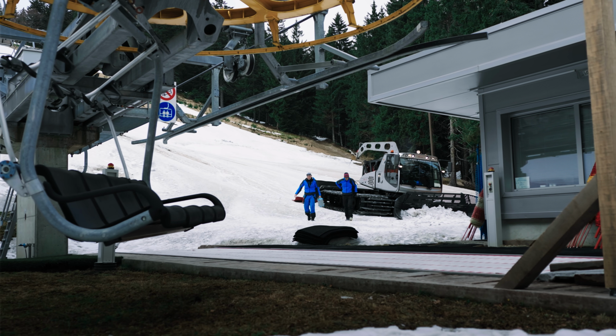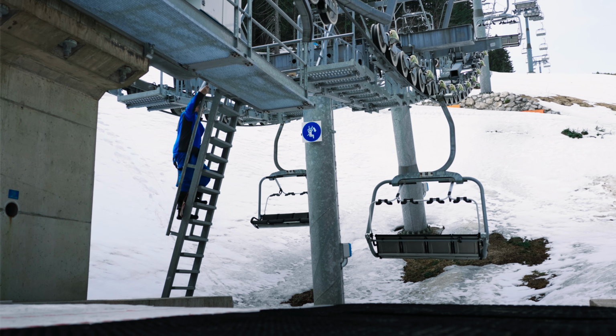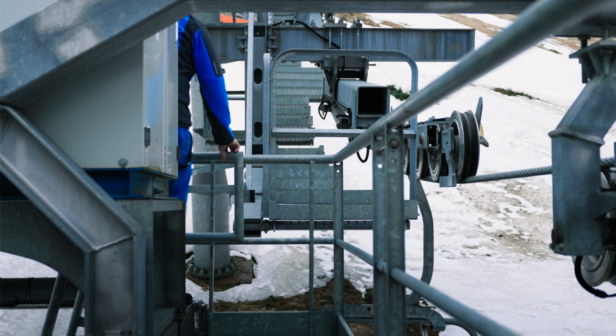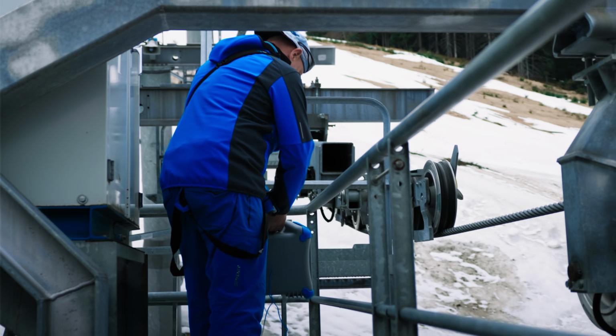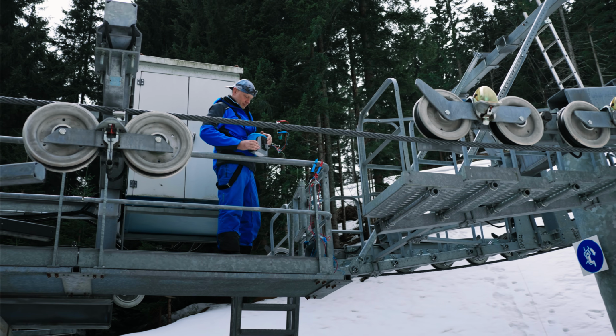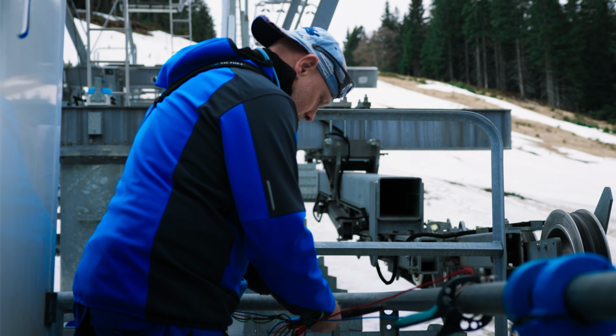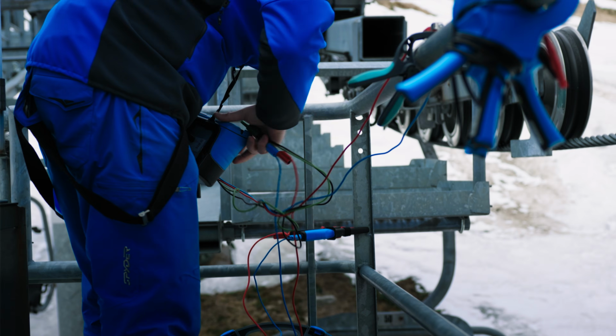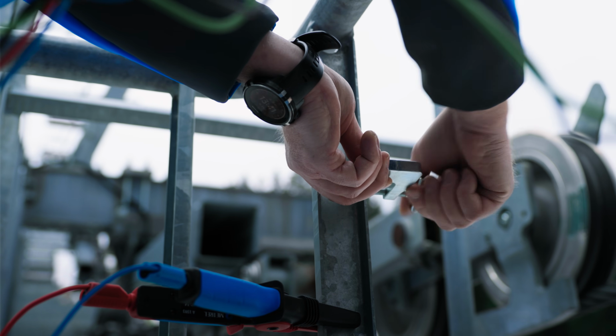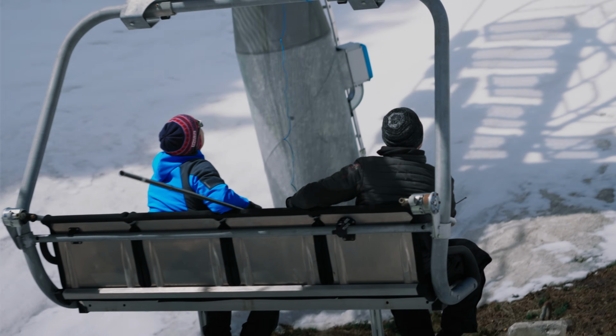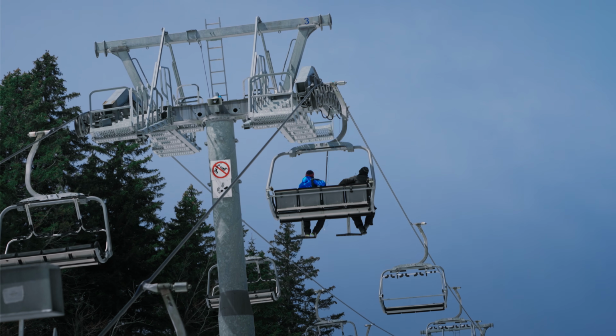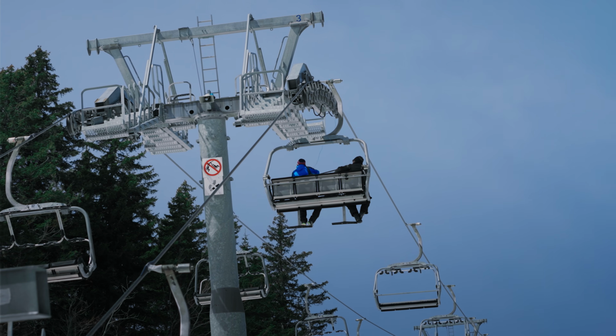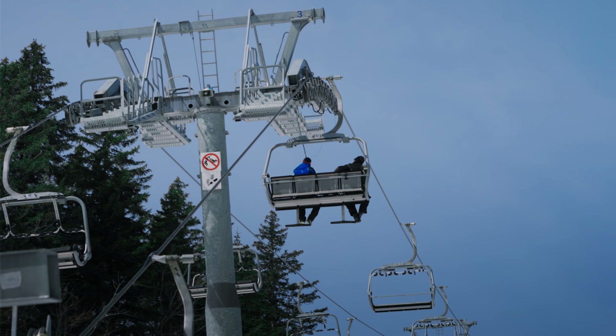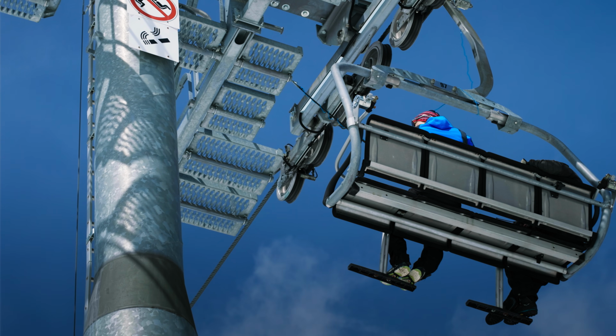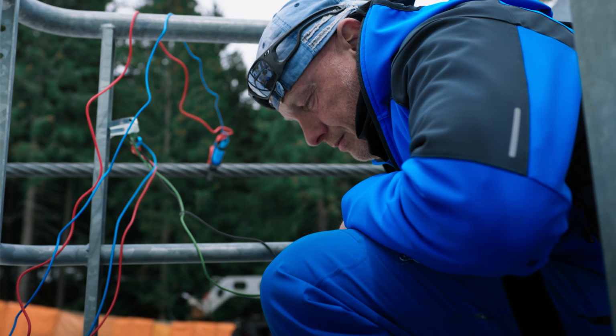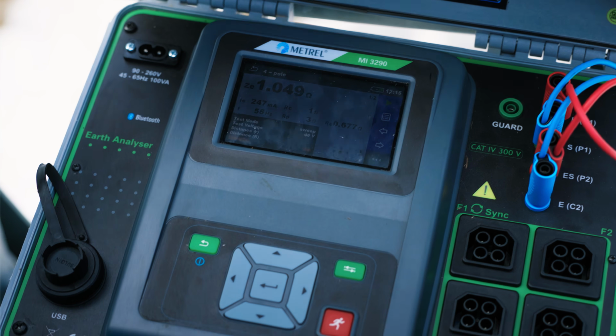Depending on the team's competencies, we choose the appropriate workflow and measuring equipment. In this case, we use either the MI3290 Earth Analyser or the MI3288 tester. All measurements are performed by the inspector at the lower station, while a team member carries out local grounding at each tower during system stops. This method gives the inspector greater flexibility to apply various testing techniques and perform comparative measurements with precision.